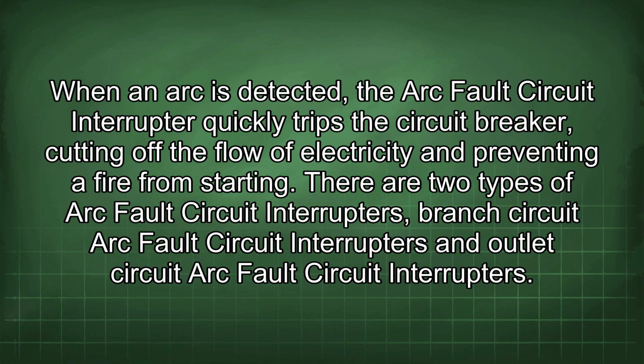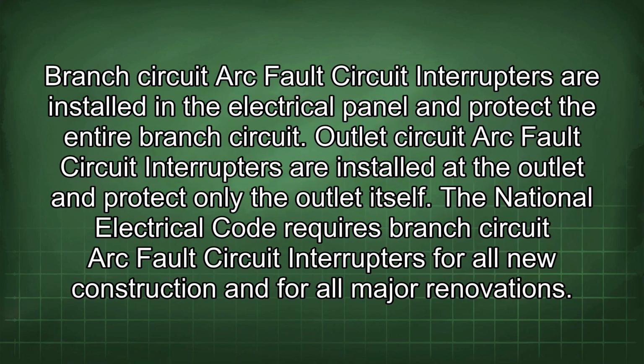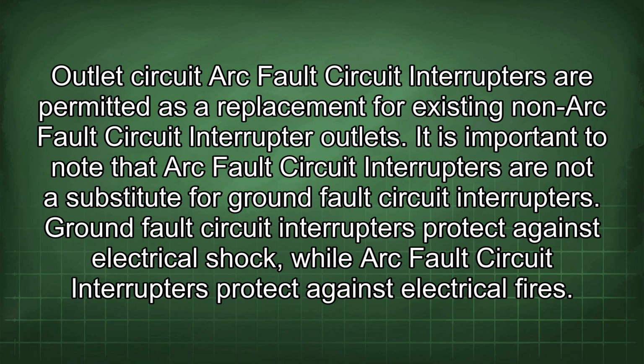There are two types of arc fault circuit interrupters: branch circuit arc fault circuit interrupters and outlet circuit arc fault circuit interrupters. Branch circuit arc fault circuit interrupters are installed in the electrical panel and protect the entire branch circuit. Outlet circuit arc fault circuit interrupters are installed at the outlet and protect only the outlet itself. The National Electrical Code requires branch circuit arc fault circuit interrupters for all new construction and for all major renovations. Outlet circuit arc fault circuit interrupters are permitted as a replacement for existing non-arc fault circuit interrupter outlets.